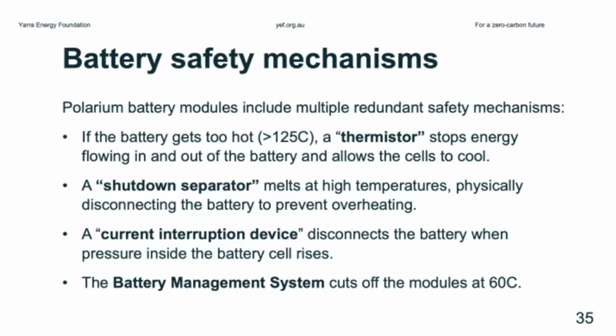Finally, the battery management system is the firmware installed in these battery modules, and it cuts off the connection at 60 degrees Celsius. 60 degrees is considered the upper limit of safe operating temperatures for these batteries, but we operate our YEF battery with a ceiling of 45 degrees, so the cooling kicks in far earlier.